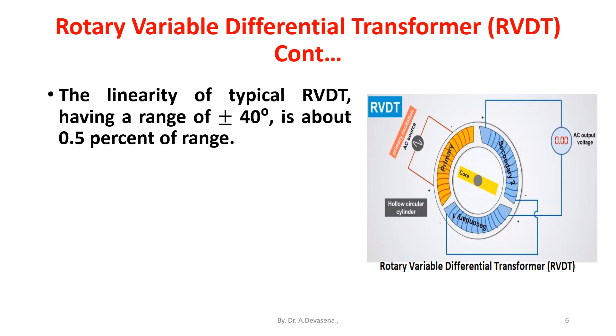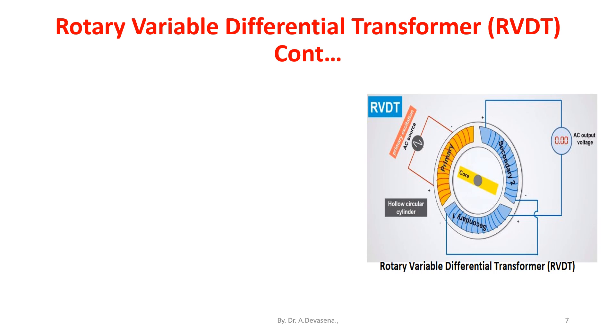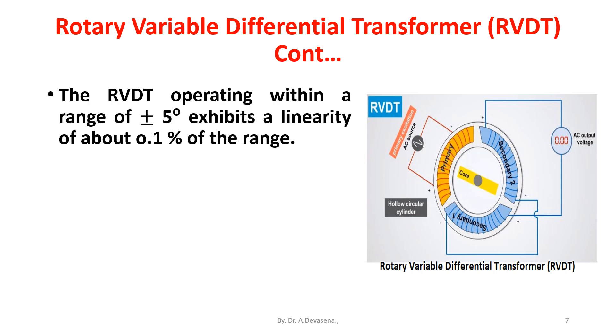Reducing the operating range improves the linearity. The RVDT operating within a range of plus or minus 5 degrees exhibits a linearity of about 0.1 percentage of this range. The advantages and disadvantages of the RVDT are similar to LVDT.